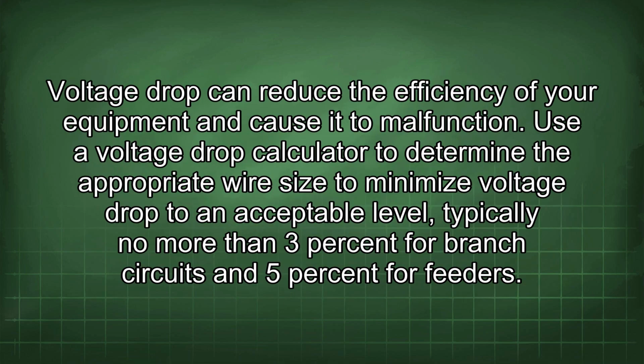Voltage drop can reduce the efficiency of your equipment and cause it to malfunction. Use a voltage drop calculator to determine the appropriate wire size to minimize voltage drop to an acceptable level, typically no more than 3% for branch circuits and 5% for feeders.